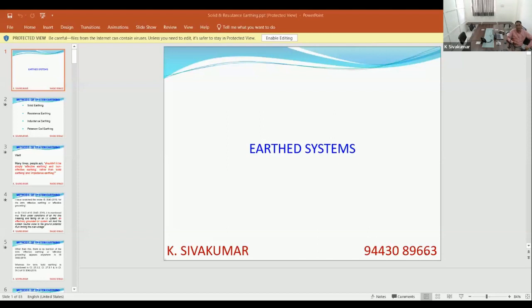We say it plays a role in system earthing. Triplen harmonics are generally anticipated in single phase electronic loads, single phase non-linear loads. Most of the data centers and computers, lighting, CFL lighting, LED lighting, fan regulators, and single phase UPS, all these things are generators of triplen harmonics. So this is the relationship of triplen harmonics with earth.